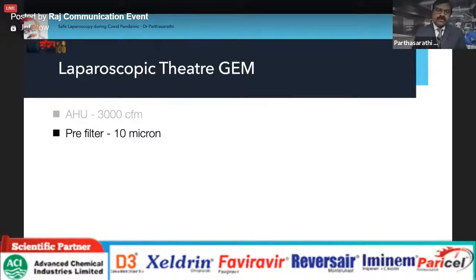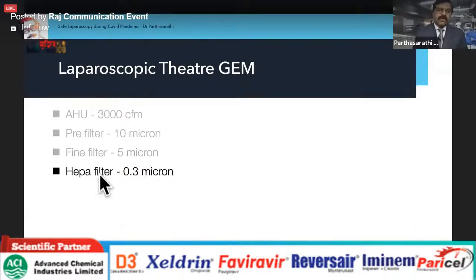And then we have filters: one is called the pre-filter, a 10 micron filter, and another is a fine filter, a 5 micron filter. Both filters are attached to the AHU just outside the OT room, and then the air comes in, and in the OT there is a HEPA filter. It filters 0.3 micron. All the filters, even our N95 mask, filter only 0.3 micron size. But the COVID virus is 0.1 to 0.2 micron, about 0.14 micron. So we don't have any filter right now that filters the COVID virus. But if you follow all the protocols, then we will be safe.